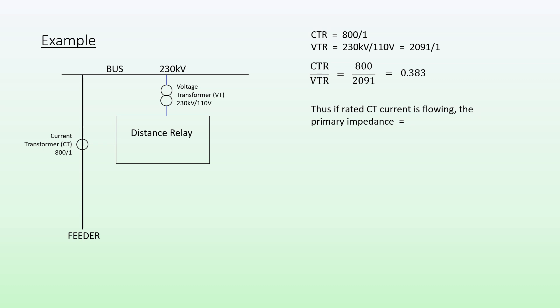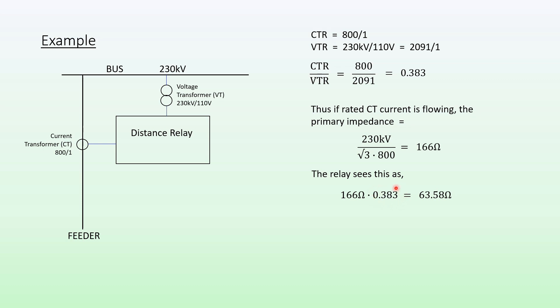If rated current is flowing — that is, 800 amps in this feeder — the primary impedance is equal to 230 kV divided by root 3, times 800, which equals 166 ohms. The relay sees this as 166 times our CT ratio divided by VT ratio constant, which gives us 63.58 ohms.